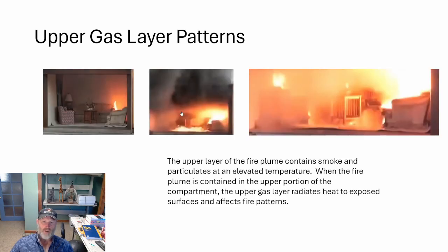Let's take a look at a compartment fire. This is just a laboratory test. A fire was started in a trash can. You can see that after a certain amount of time, it's actually just a few minutes, you see a fairly stable lower smoke boundary. And then you see the whole building basically become a very hot fire. You see fires in locations all over the place. But more importantly, look at the floor. You see how it's really smoking hard. A lot of pyrolysis there. This is ready to just explode and flash over.